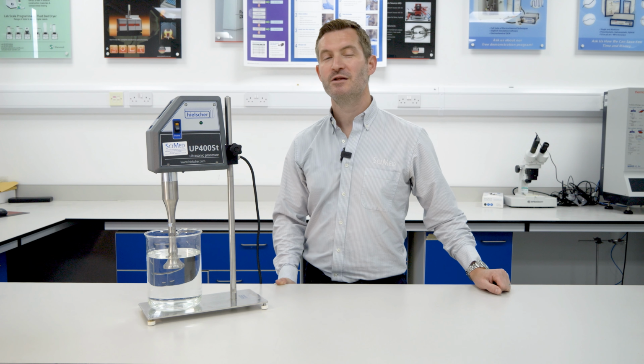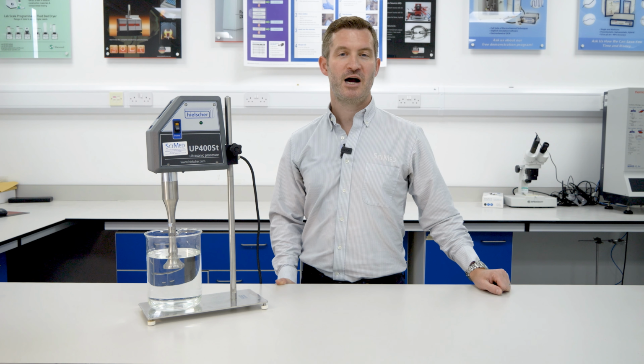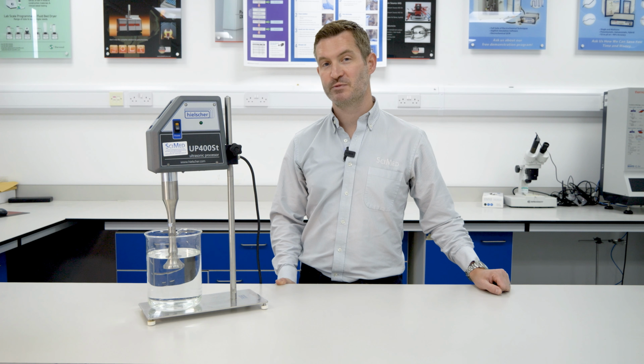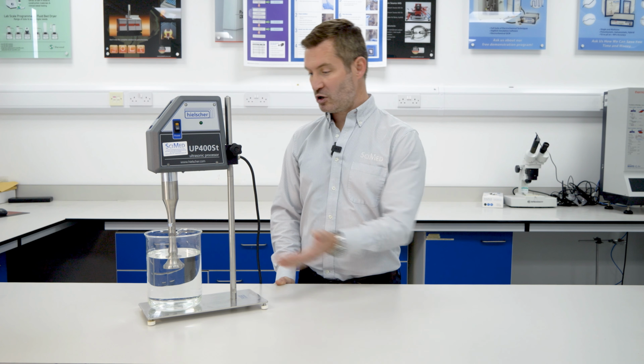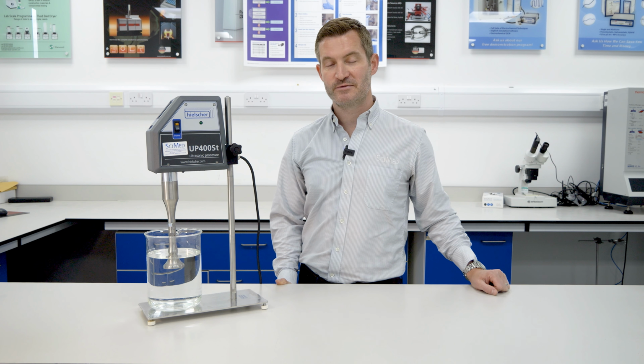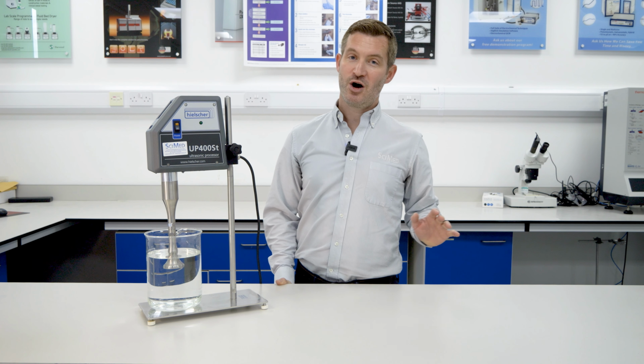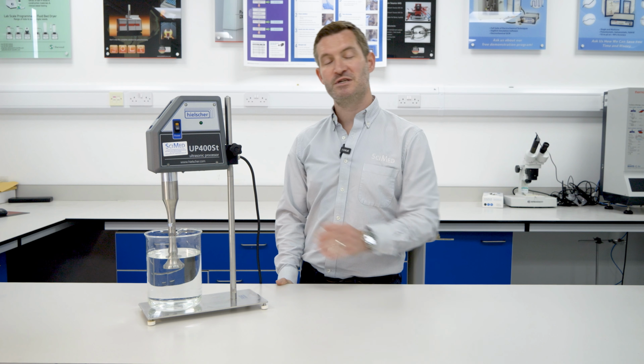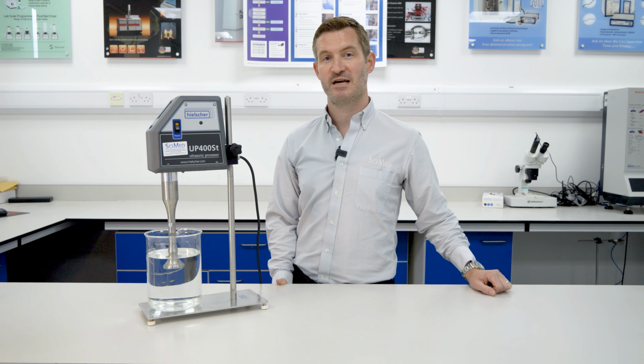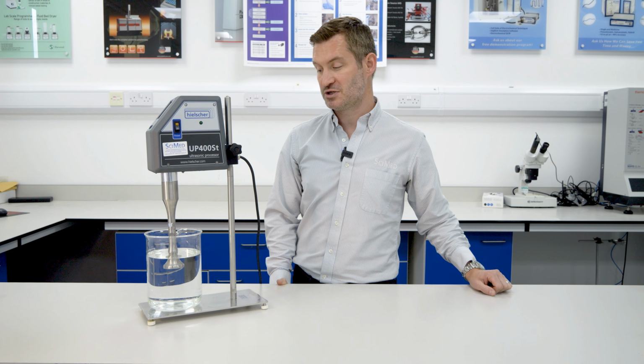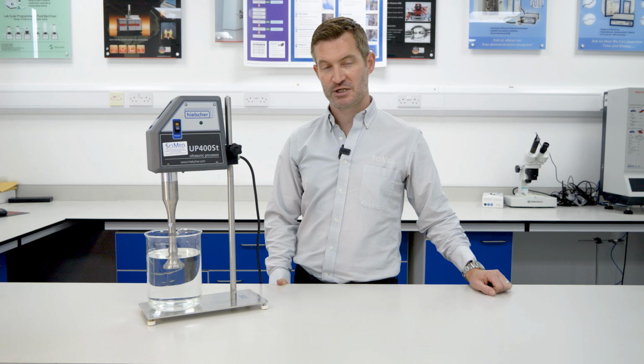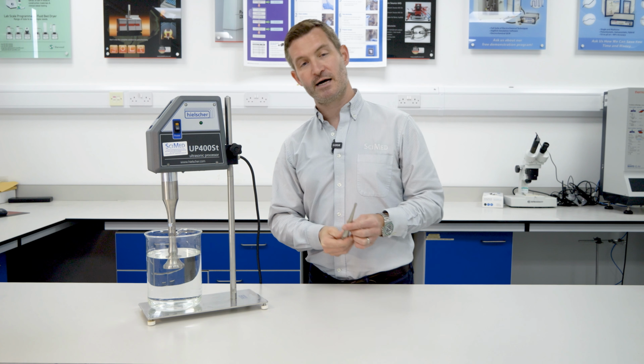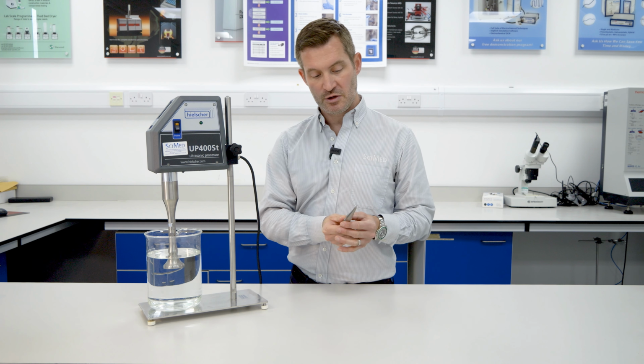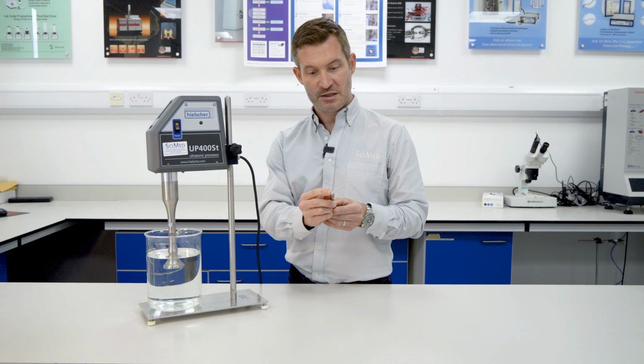Frequently asked question number 3: how often do I have to replace my probe tip? Probe tips are made of solid grade 5 titanium—really tough, corrosion resistant, and hard wearing. If you're not using your instrument 24/7 for production, those tips should last you a couple of years each, at least. You can always tell the condition of a probe tip by looking right at the end of the probe and studying it.